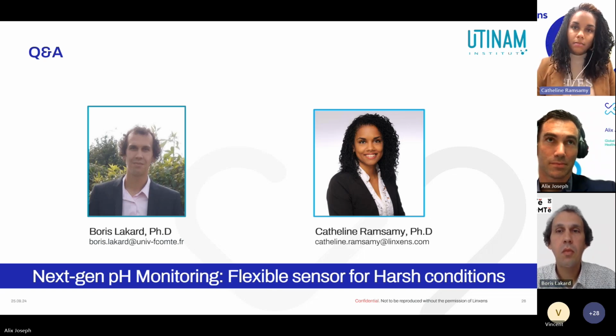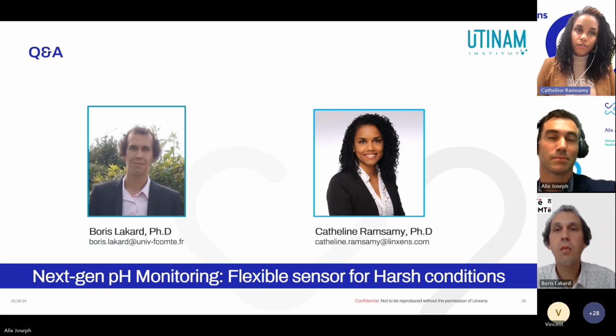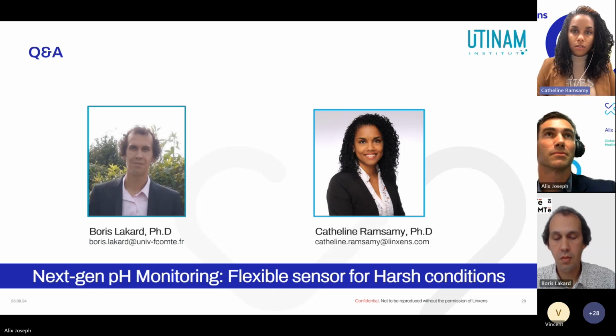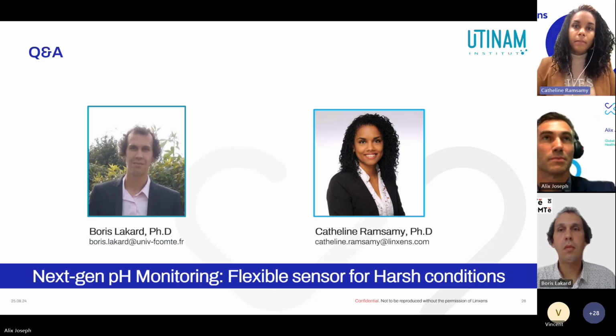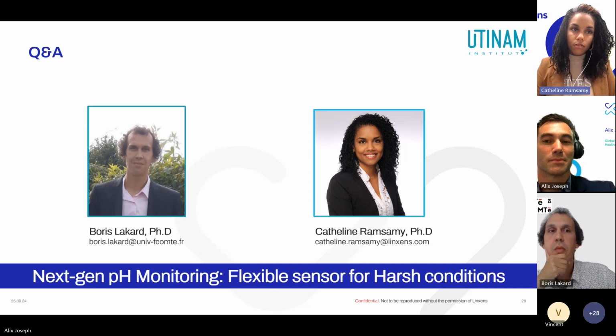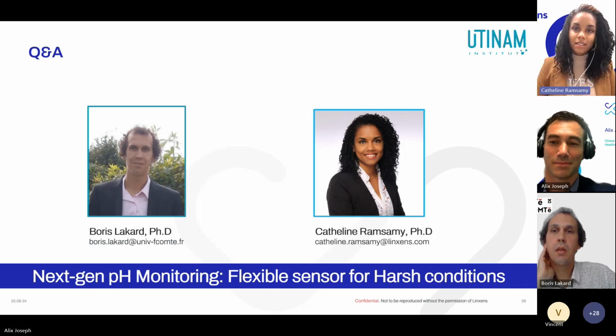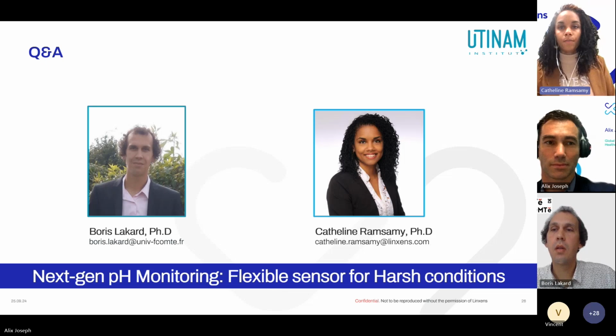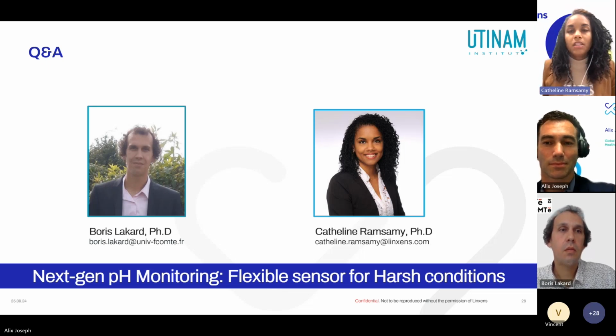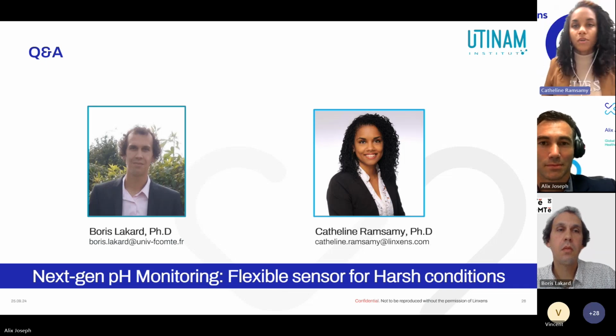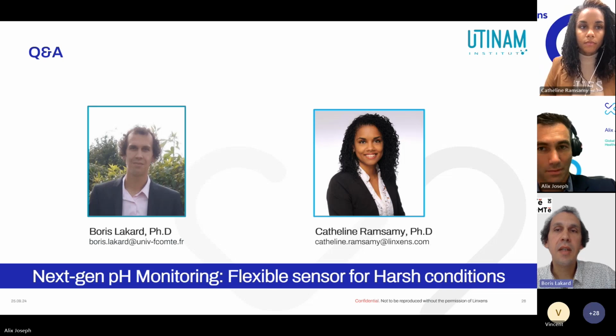For some customers, we tested this parameter, and there is no impact of salts on the performance of the pH sensors. The only thing is that as it is a potentiometric sensor, if you considerably increase the conductivity of the solutions with sodium, we need to take care of this and take it into account during the measurement. But we tested in the range of sweat sensors, so the sweat concentration of sodium chloride. With this range of usage, we don't see any impact of the sodium concentration on the performance of the pH sensor. In fact, it can modify the ionic strength, and it can also modify the potential, but I think it's not a big change.